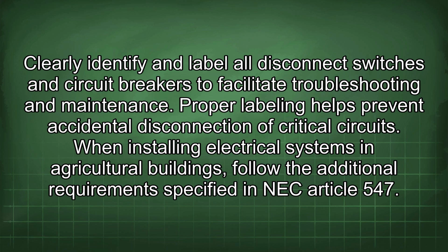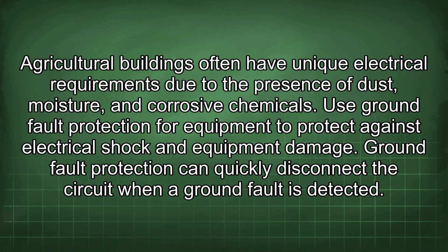When installing electrical systems in agricultural buildings, follow the additional requirements specified in NEC Article 547. Agricultural buildings often have unique electrical requirements due to the presence of dust, moisture, and corrosive chemicals. Use ground fault protection for equipment to protect against electrical shock and equipment damage. Ground fault protection can quickly disconnect the circuit when a ground fault is detected.